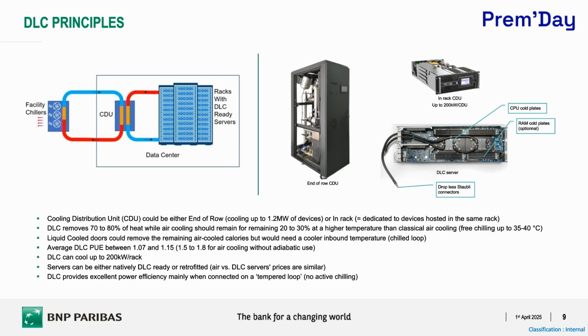Okay, so DLC. Maybe I will do overkill there because it's quite simple in principle, so I will go fast. Basically, you have a CDU, which is a heat exchanger, as you may have in nuclear power plants, for instance. You have a circuit on the left, which is taking the calories outside of the facility, and a circuit on the right, which is bringing the liquid into the racks and into the servers. There are different systems with CDUs which are outside of the racks, which are called end of row, and there are also small CDUs that you can plug into each rack.